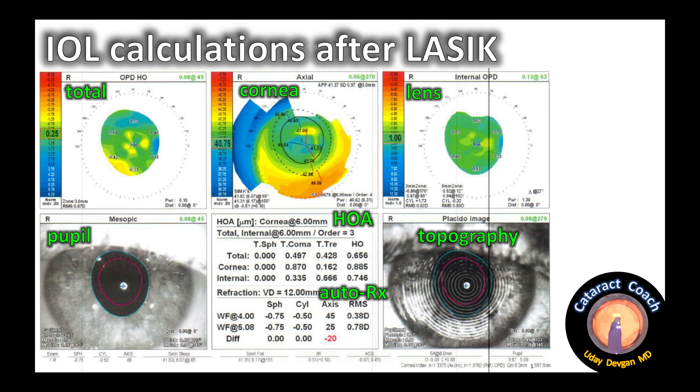It also shows the higher order aberrations (HOAs) at the central 6mm of the cornea. Remember Zernike polynomials: lower order aberrations are sphere and cylinder — what you can fix in a refraction. Higher order aberrations such as spherical aberration are the fourth Zernike polynomial term. The bottom right corner is Placido disc topography — reflection off the surface of the cornea — and that data is used to calculate the topographic map.